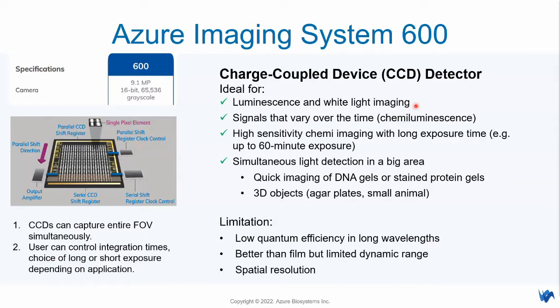CCD detector is still the best detector for chemiluminescence signals because it can capture the total field of view, and is ideal for luminescence and white light imaging. Signals that vary across time — like chemiluminescence — can be set at a certain exposure time, up to 60 minutes. Simultaneous light detection in a large area allows you to capture the entire image of a gel, protein gel, DNA gel, or even 3D objects. The CCD camera's limitation is lower quantum efficiency at wavelengths longer than 800 nanometers, and spatial resolution is heavily dependent on the camera's resolution.